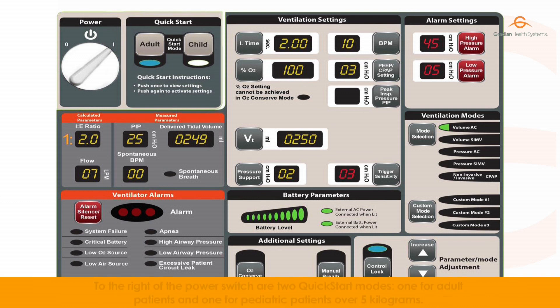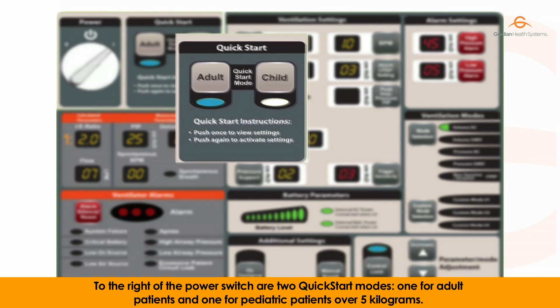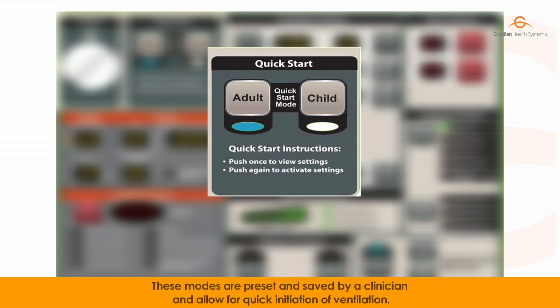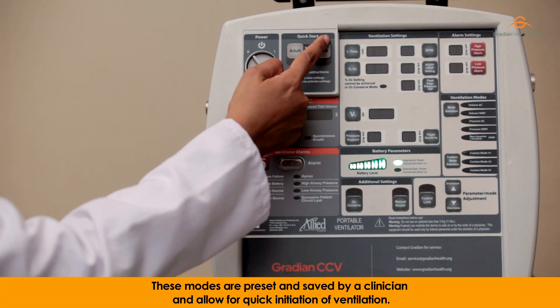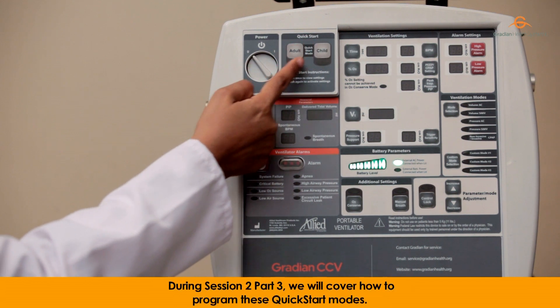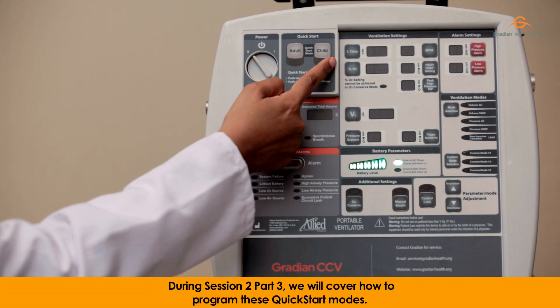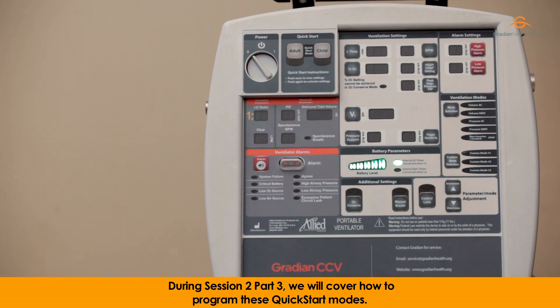To the right of the power switch are two quick start modes, one for adult patients and one for pediatric patients over five kilograms. These modes are preset and saved by a clinician and allow for quick initiation of ventilation. During session two, part three, we will cover how to program these quick start modes.